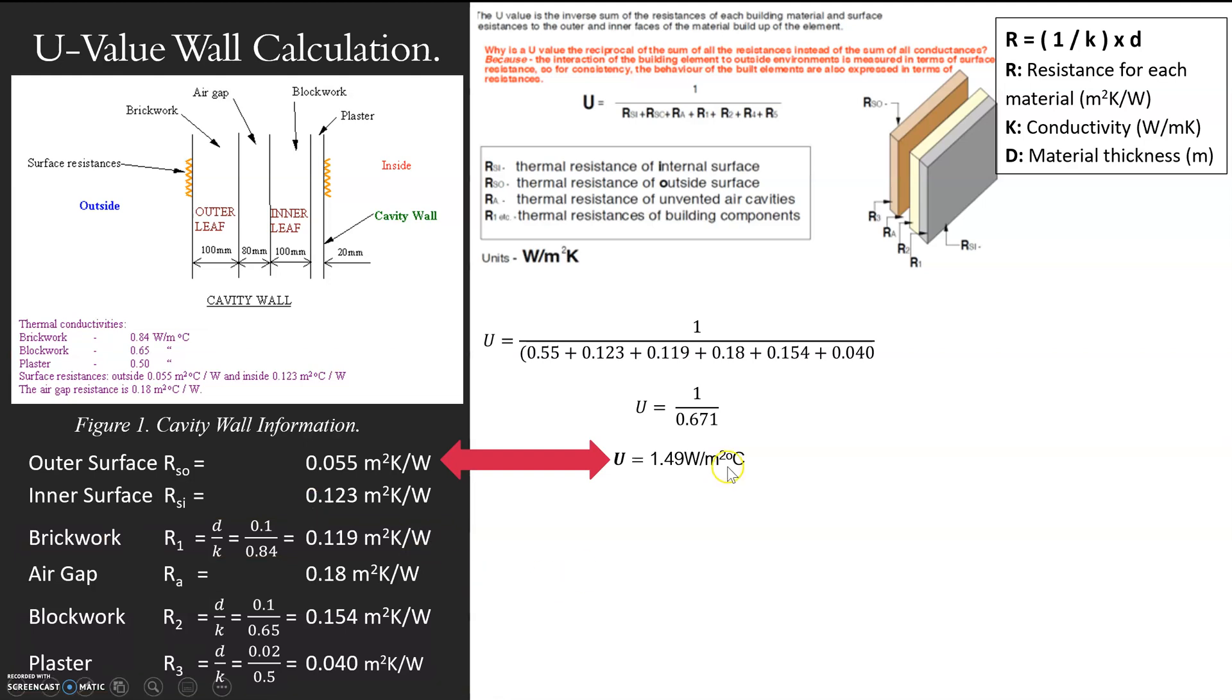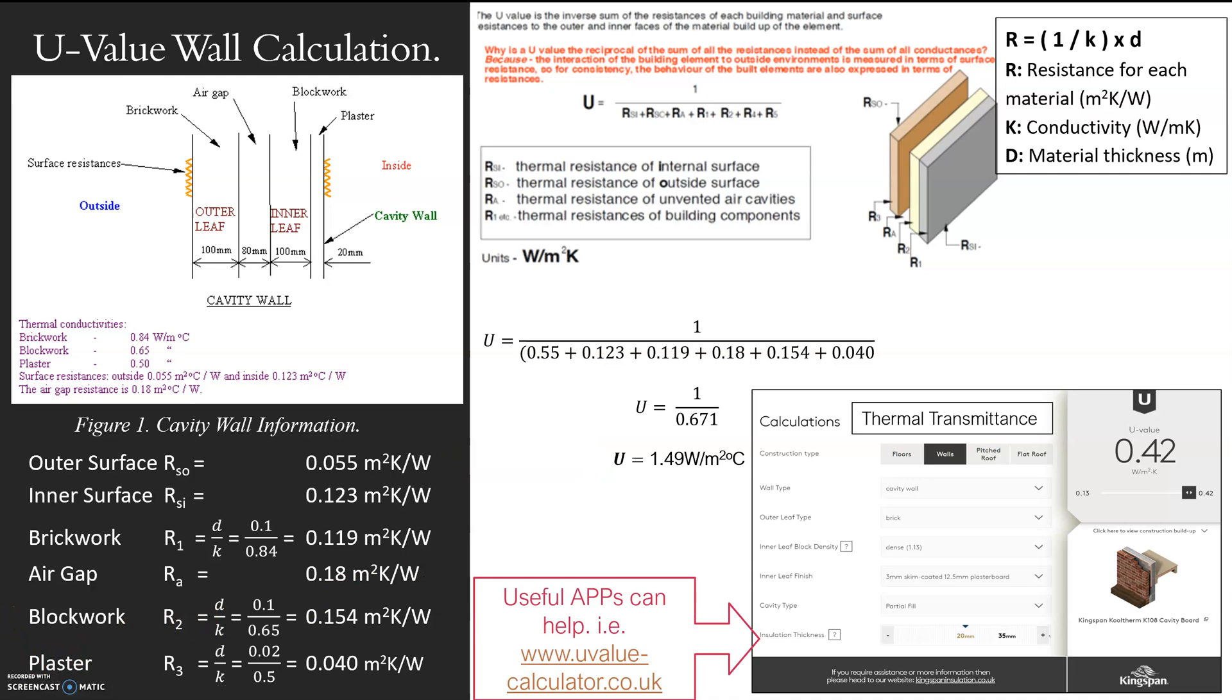So then I move on and now I've got all the resistances of all the materials. I can add them all together and I can put them into my lovely U-value formula here. So I have my U-value, 1.49 watts per metre squared. I've put degrees Celsius because that's what I'm measuring in on this wall.